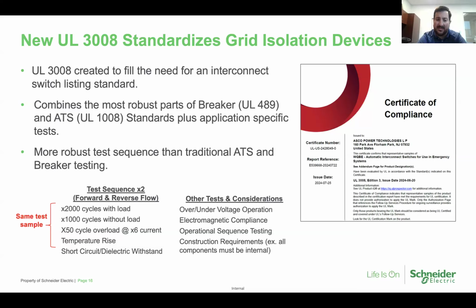And the thing is, it's a very robust standard. Going back to the comparison to UL 1008, which is really the golden standard for transfer switching that everyone thinks about when they think about resiliency and standby power switching, it aligns more closely to that when it comes to the performance qualifications of the product than UL 489. Some of the tests that are included in there are things like cycle testing with and without load, overload testing if you're putting overcurrent on the equipment, temperature rise testing to make sure it can hold up, of course, short circuit and dielectric testing to make sure it can handle a downstream fault if one happens. But where it takes more inspiration from 1008 versus UL 489 is the fact that in UL 489, when you're qualifying a breaker, each of those tests can happen on a physically separate sample for the test. So each test you do, you're starting off with a pristine sample.